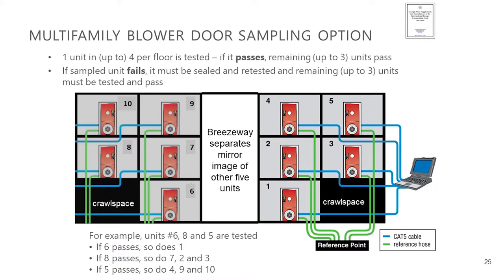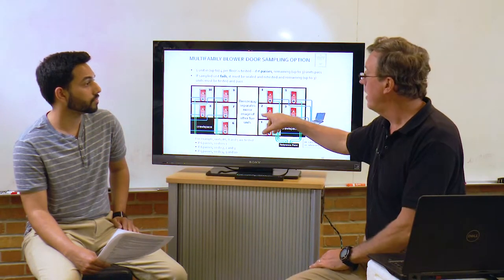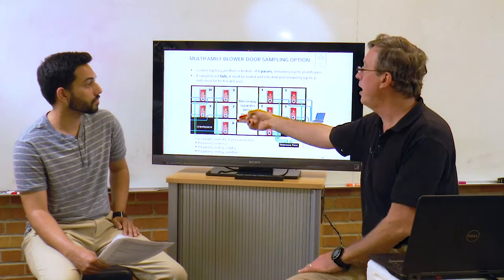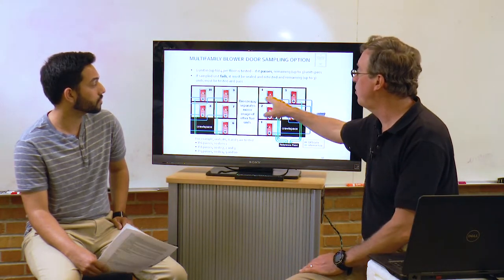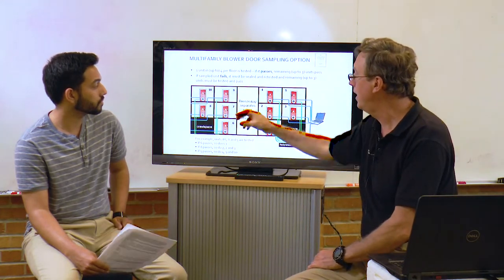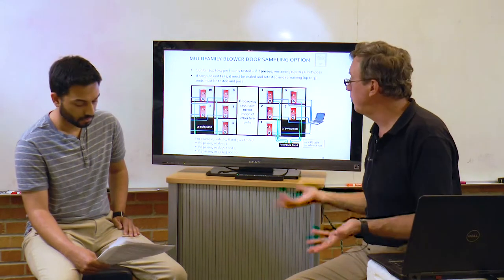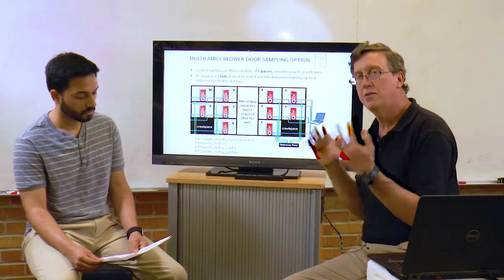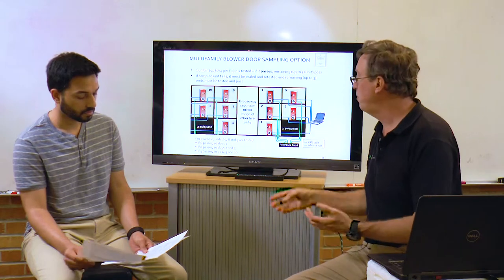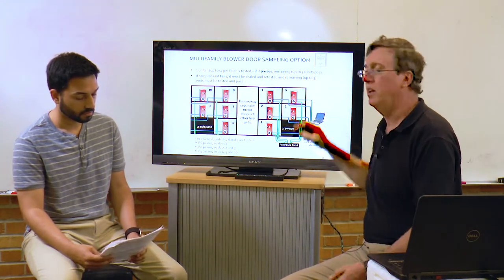But the batch concept of sample testing says, I'm gonna create a batch of up to four units in a batch. They have to be on the same floor adjacent units. And here I would probably have a batch of unit 5, 4, 9, and 10. I would have another batch of units 3, 2, 7, and 8. And then the third batch would be units 1 and 6. If I blower door test, for example, unit 6 and it passes, so does unit 1. If I blower door test unit 8 and it passes, so does 7, 2, and 3.